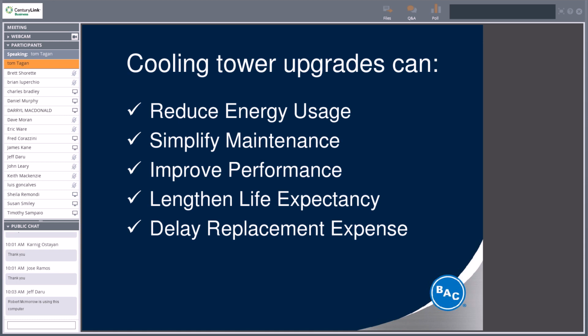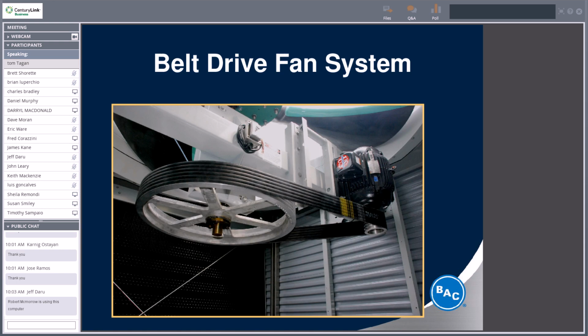Cooling tower upgrades can reduce energy usage, simplify maintenance, improve performance, lengthen life expectancy, and delay replacement expense. Fan belt drive system, I think this kind of shows you the heavy-duty industrial gauge that these belts are. I believe we provide belts up to 75 horsepower, at least up to 50. Sometimes on the big towers, 75 to 100. You need the gear to get that big fan started. But we have no hesitation providing at least up to 50, 60 horsepower.